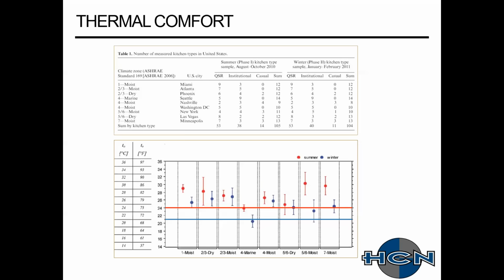So ASHRAE actually set out and did a report on thermal comfort for kitchen environments, basically from August 2010 to February 2011. And they covered quick service, institutional, and casual, kind of went over all of that stuff. As you can see from here, the red line is 75 degrees, the blue line is 72 degrees. It didn't matter what environment, what zone. You can see from here, in most kitchen environments, everyone's saying they're pretty warm or uncomfortable.